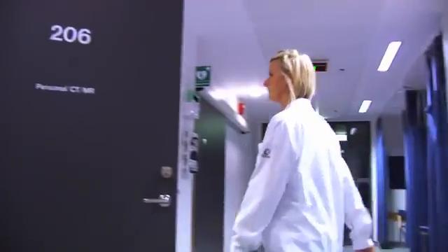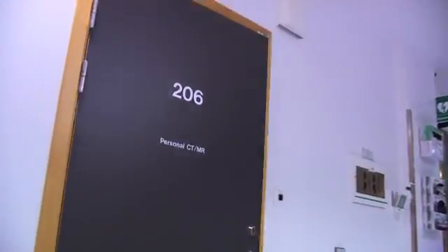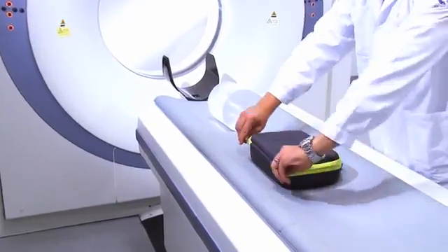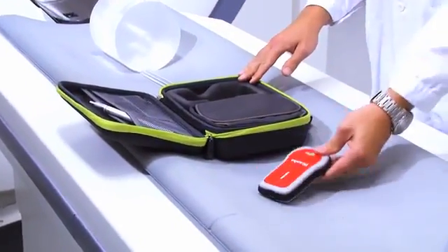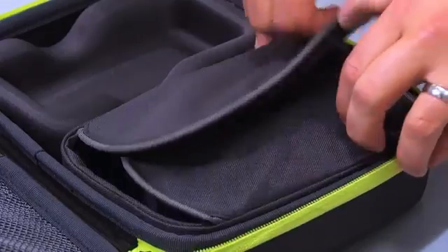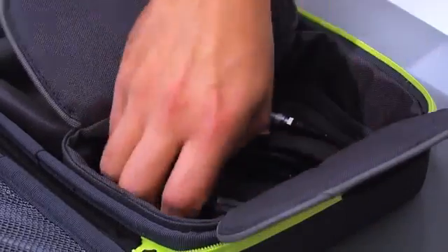The rapid developments in CT technology are placing new demands on the methods and equipment used for quality assurance. With standard CT ionization chambers, you are only getting a limited dose value for 10 cm. The CT dose profiler has been developed to resolve this problem as it provides a dose value for an unlimited length.